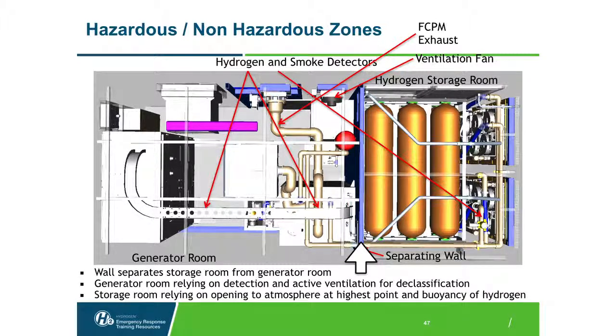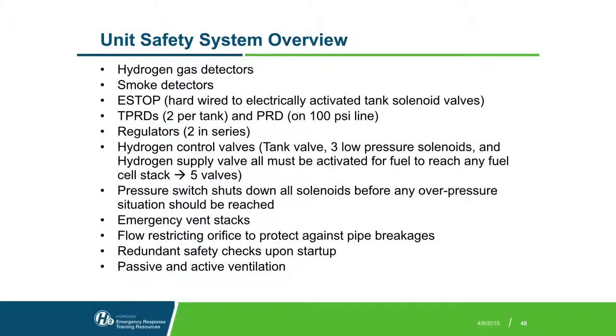So in terms of separating these zones, the generator room is relying on the detection and active ventilation for declassification, and the storage room is relying on being open to atmosphere, as well as that slanted roof that would allow any leaking hydrogen to vent out. So redundant and multiple safety systems included on this unit include the hydrogen and gas sensors, the e-stops, thermally activated pressure relief devices, 2 per tank. Again, 1 on each end of the tank. So if you had fire on one side or the other, those are designed to vent the contents.